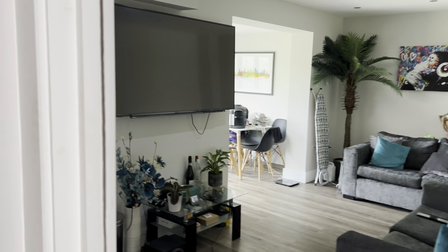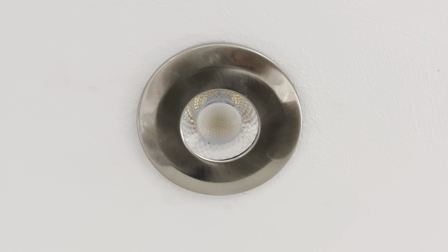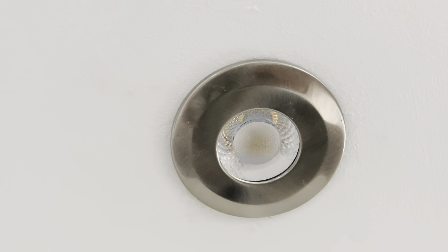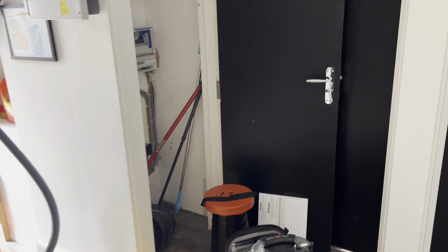So if I now come back over to the light fittings in the room I showed you before — we've still got power at these light fittings, we've still got something going on. There's something clearly adrift because we've still got this dim LED light coming off them. We do have dimmers in here and they can cause havoc sometimes, but it's all the way around the property, even in rooms that don't have dimmers. So we've got to rule that out.